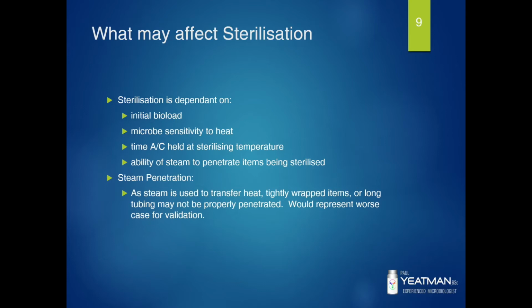Steam penetration. Well, steam needs to penetrate items in order to transfer its energy. So a bottle with a lid tightly screwed on won't allow steam to enter it. A long hose may not allow steam to get all the way to the centre of the hose. And tightly wrapped equipment may not allow steam to fully penetrate the wrap. And they also may not allow for complete circulation of steam around them, so incomplete penetration could occur.